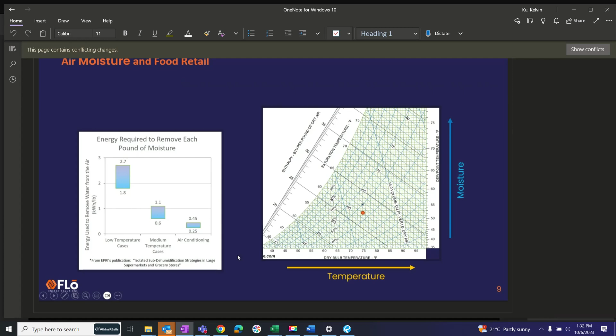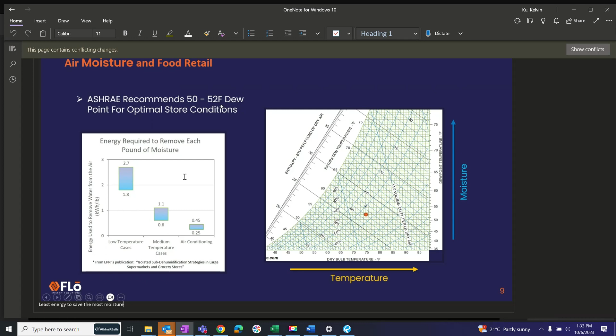ASHRAE recommends a 50 to 52 degree dew point as the optimal for stores. This is the point at which we're using the least amount of HVAC energy to save the most amount of refrigeration energy. If we make it drier, we need to spend more energy to make it drier, and the refrigeration system will save a little more energy, but not as much. And so there's this crossover point. And if we don't dehumidify to this level, the refrigeration equipment's energy goes up exponentially.